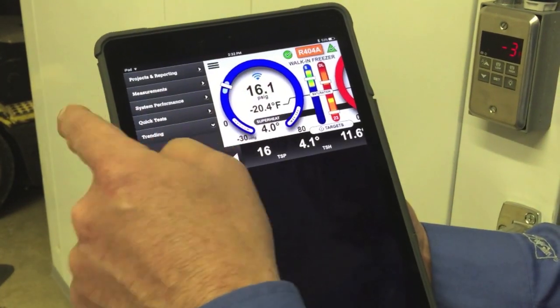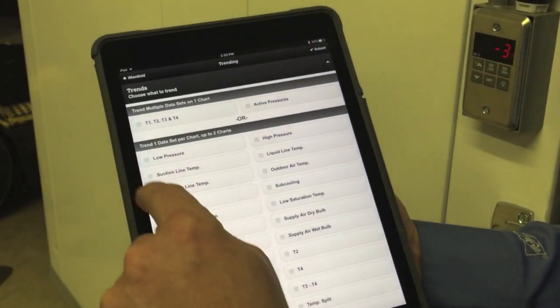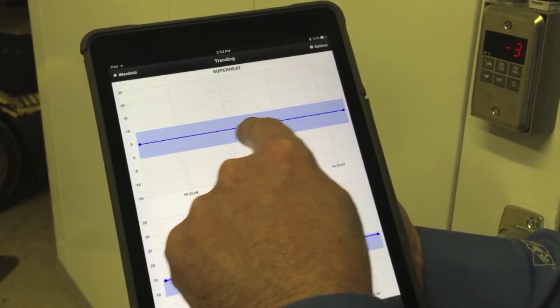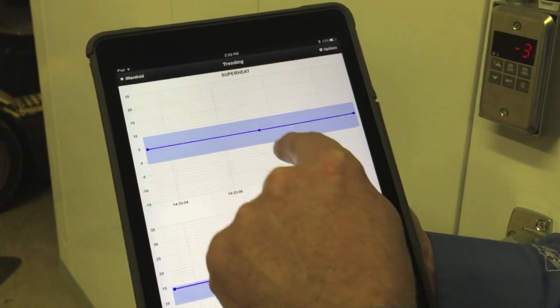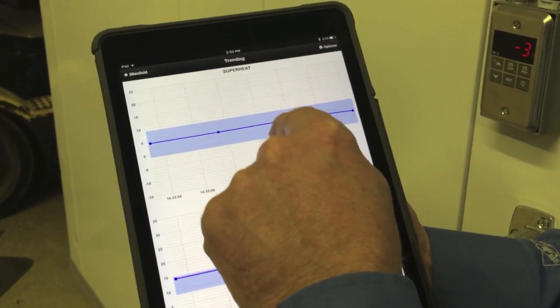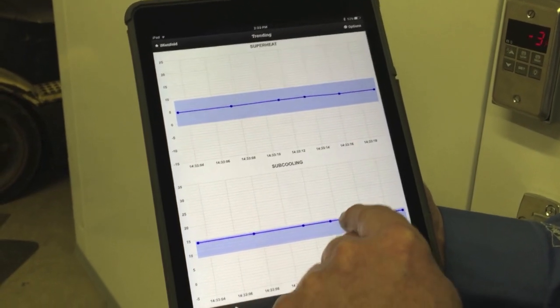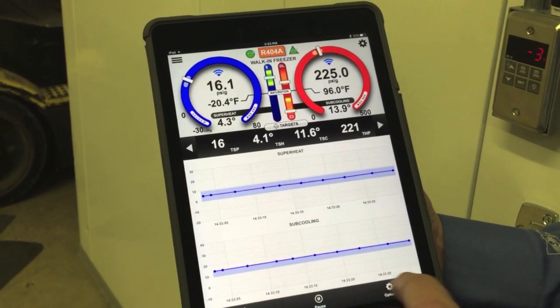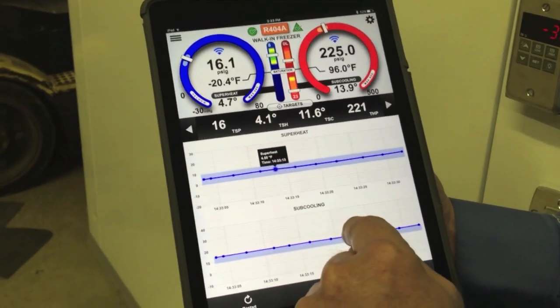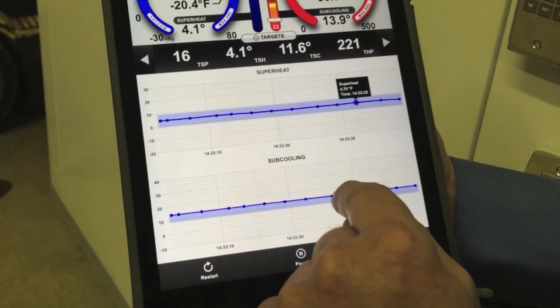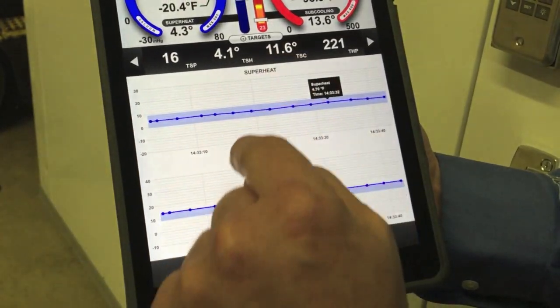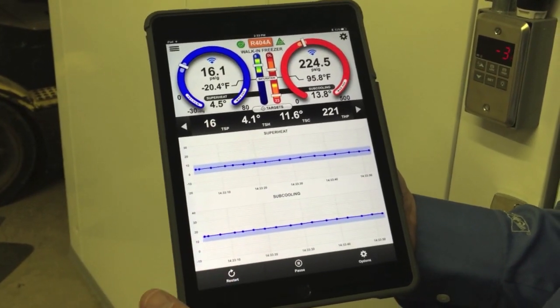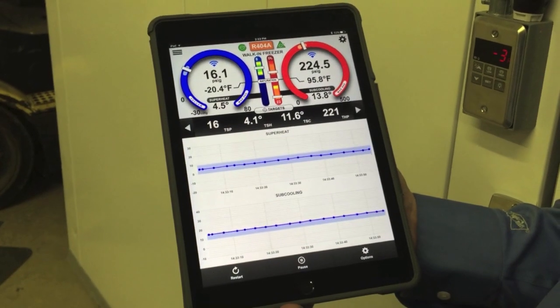Another cool thing we can do is trending, to make sure things are stable. I'm going to set up some trends here — we're going to trend the superheat and subcooling. Hit submit. Right away it starts trending the system and shows boxes indicating the allowable ranges: allowable superheat is plus or minus 5 degrees, allowable subcooling is plus or minus 3 degrees — and we're within the allowable range of that, so everything's okay. Going to hit I-Manifold to get the I-Manifold screen plus trends so we can watch them as they go. If we want to see what any point is on the graph, just tap it — in this case, 4.5 degrees of superheat, 4.7 degrees of superheat. It's a very quick way of visualizing how everything's running and confirming the system is running just as well today as the day we commissioned it.